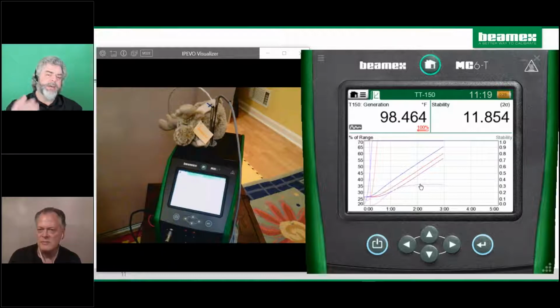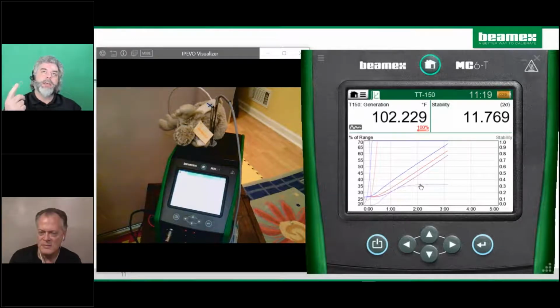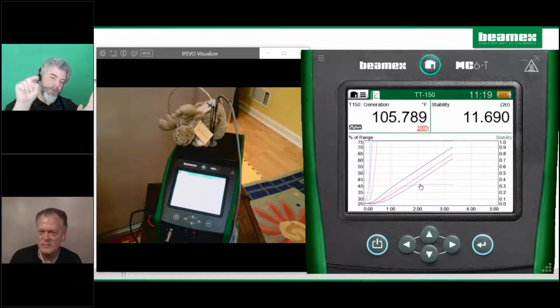And one thing I'd like to point out is we are doing a 2-point test, but we're also doing a group calibration where we are recording 3 different things: the temperature for the probe, the milliamp output, and the DCS reading. If you didn't need a loop calibration like this, you could calibrate the probe and the transmitter milliamp output as a completely automated process where you press start and it does everything, all the measurements, all the recording, and you walk away and you come back when it's done. Because we do have this DCS display, there is a manual intervention where we have to punch in what the DCS is showing.